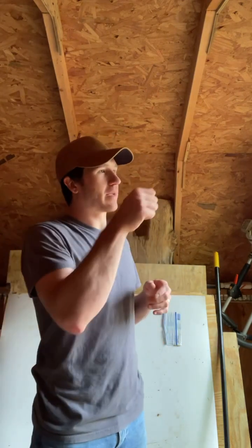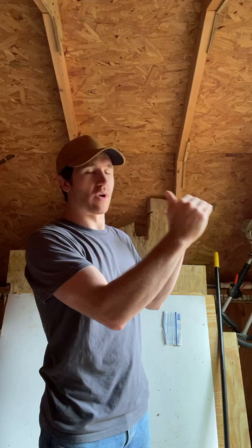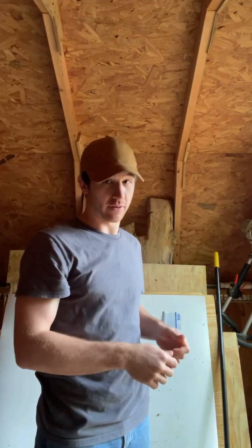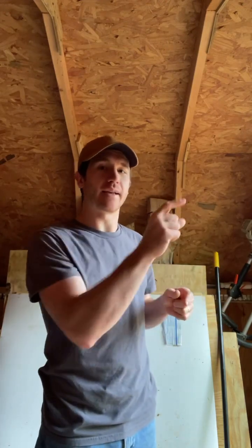All right, so you just check every breaker. You've already made sure all the breakers are on. Now you're checking every single wire that comes off of every breaker. Every wire coming off of every breaker should be indicating power. So you're touching that hot pin to every wire coming off of every breaker. And if you find that the breaker's on, but there's no power going out of that wire, well, then now you know that your circuit breaker itself is actually burnt up.